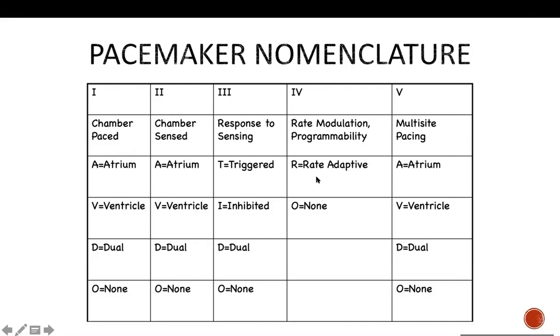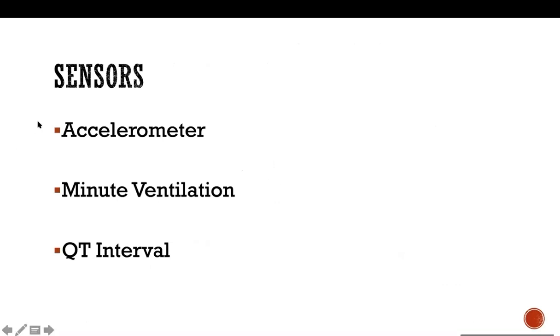The device itself would sense that there is increased activity and that the patient needs an increased heart rate based on this activity. The sensor that the device uses is an accelerometer. The accelerometer is usually triggered by the device when someone moves his arm during walking. Your arm swinging moves part of the chest, which gets transmitted to the device, and that's when the device knows that there is some activity, so it will start increasing its demand heart rate.